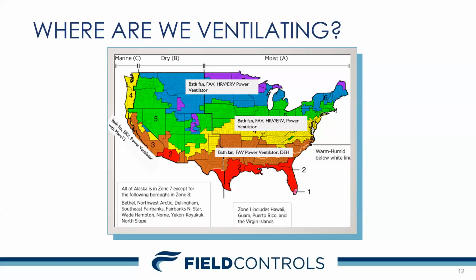You'll typically see a ventilator code as well as providing that control, whether it be a thermostat that initiates the ventilation call or a subsidiary control. What we find to be the most successful in that type of environment is a subsidiary control, because by the time the air reaches the thermostat, for it to balance out in temperature and humidity, it's often too late around a 2,400 square foot home where the bedroom gets a good percentage of that air and the thermostat is placed in a common area. It presents itself to being too late by the time the air in the thermostat is satisfied for ventilation. The other areas of the home have become too humid or too uncomfortable.